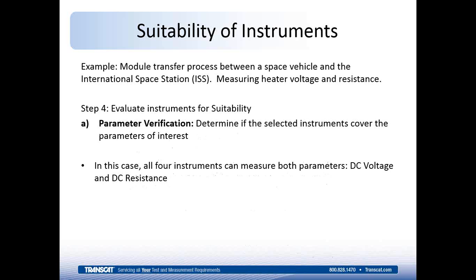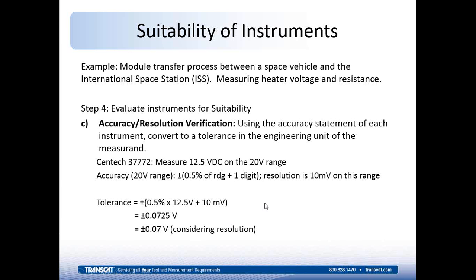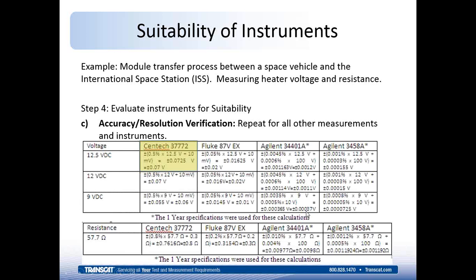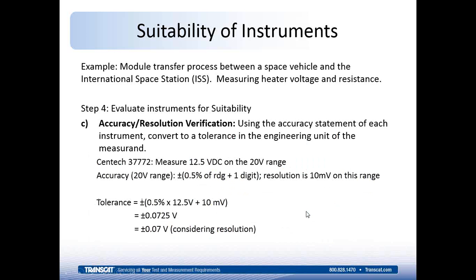All right, so then the next step is to evaluate not just the ranges, but the accuracy and resolution of the instruments. So then, using the example of the Centech 37772 and measuring the 12.5 volt signal on the 20 volt range of that instrument, the accuracy statement from the manufacturer says that 20 volt range has an accuracy of 0.5% of the reading plus 1 digit. And we know also that the resolution on that range is 10 millivolts.